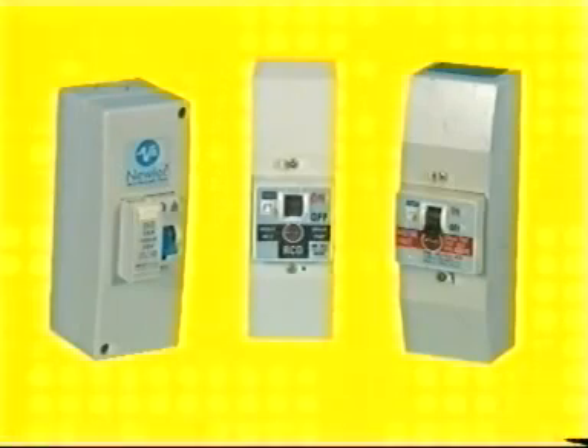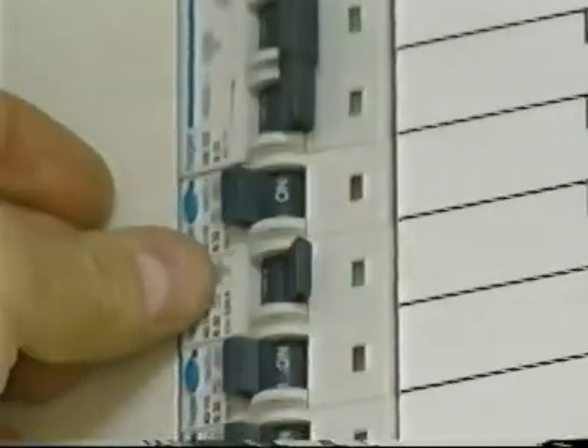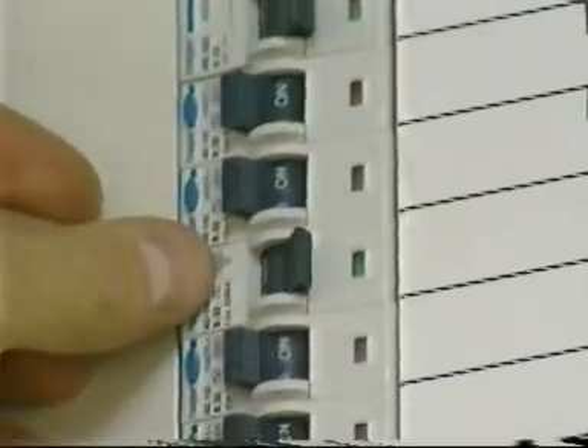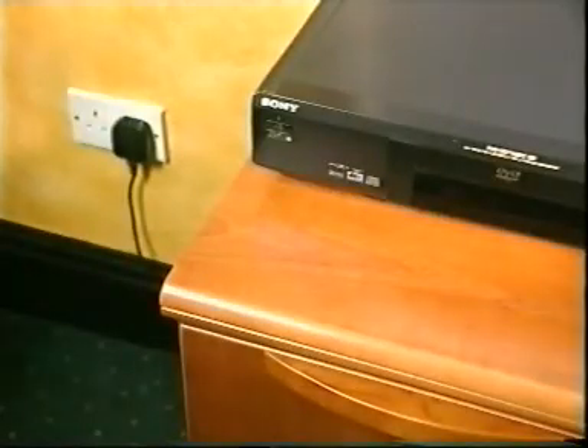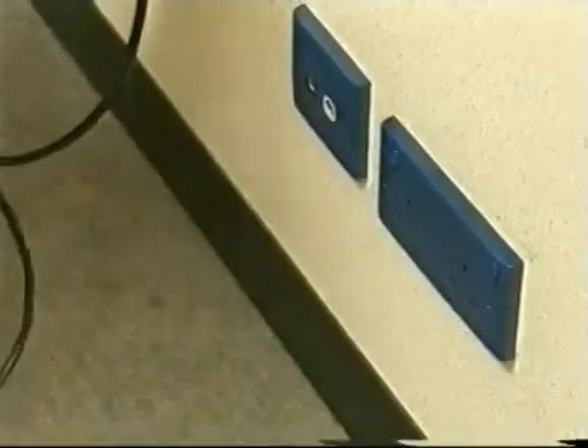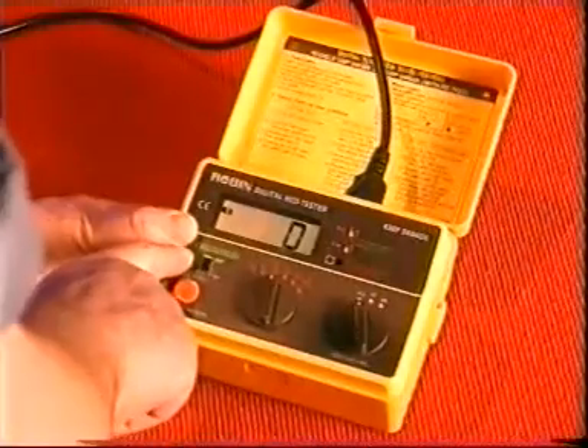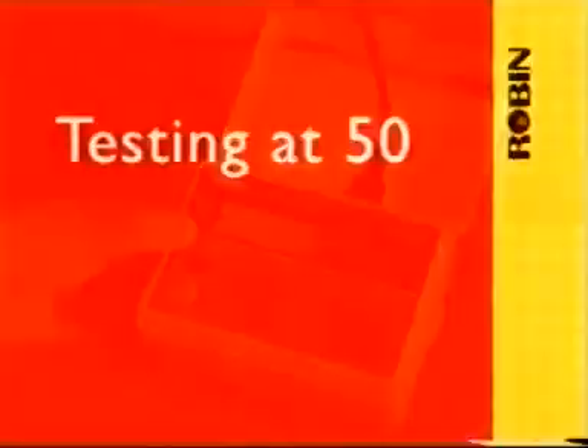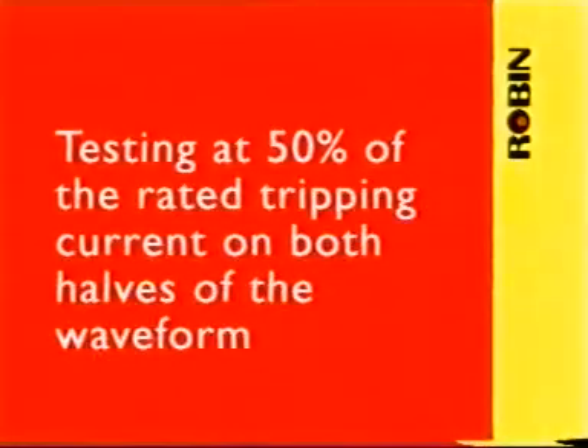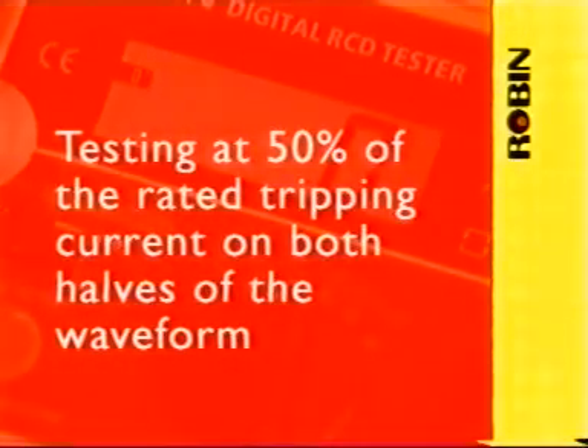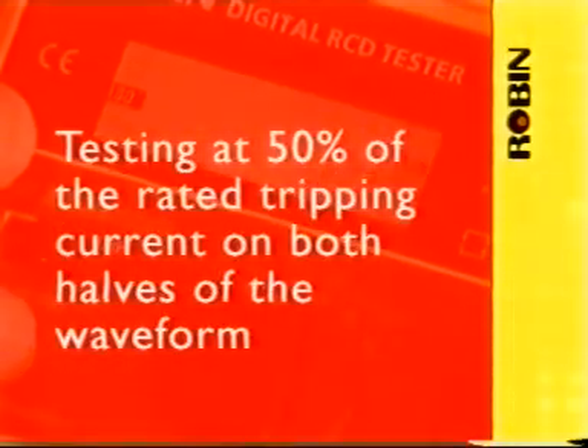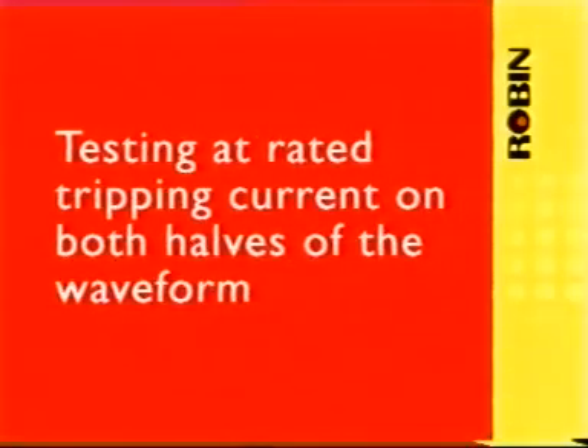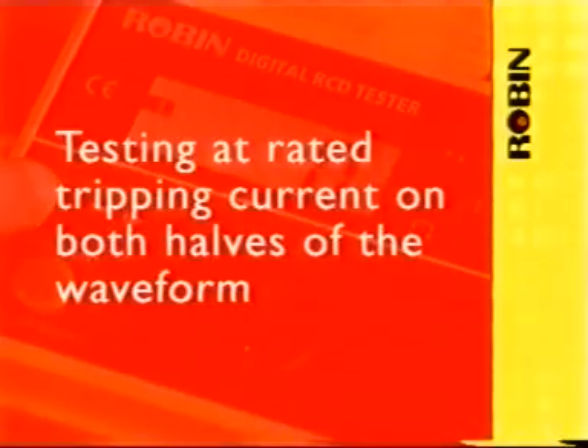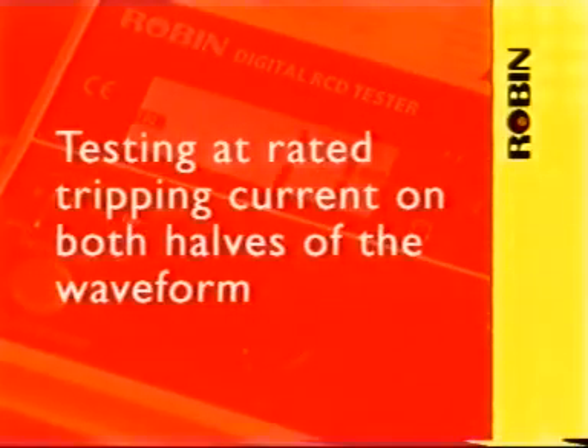BS7671 requires the effectiveness of residual current-operated devices, including RCBOs, to be verified by a test method independent of any test facility provided in the device. With loads disconnected from the circuit, the RCD tester is connected to a circuit outlet and tests performed. The RCD is normally tested on the positive and negative half cycles of the supply waveform, 0 degrees and 180 degrees. Some RCDs may be less sensitive and slower to operate in one half of the waveform to the other. Two values are taken, and if different, the longer time is recorded.